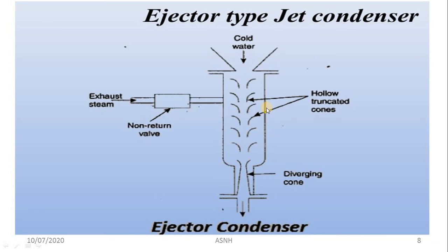So this is the construction of the ejector type condenser. The steam is coming from the top side of the shell, or a little bit upper part of the middle section, and the cooling water from the cooling water pond or from the cooling tower enters from the top of the shell. The mixing of steam and water takes place, and the mixture passes through the n number of hollow truncated cones, where the pressure energy of the mixture gets converted into kinetic energy, and at the end a long single divergent cone is provided. Here the kinetic energy again gets converted into pressure energy, and due to that pressure, the condensate enters directly into the hot well in the absence of the condensate extraction pump.